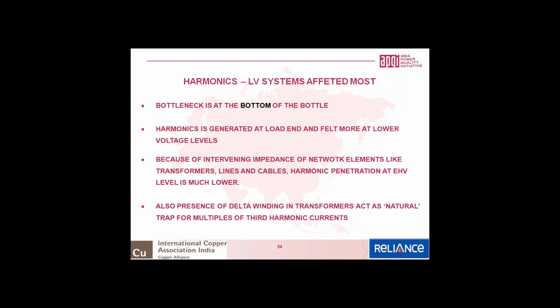As we say, usually the bottleneck is at the top of the bottle, but in this system the bottleneck is at the bottom of the bottle. Harmonics is generated at the load end and felt more at lower voltage levels because of the intervening impedance of network elements like transformers, lines and cables. Harmonic penetration at EHV level is much lower.